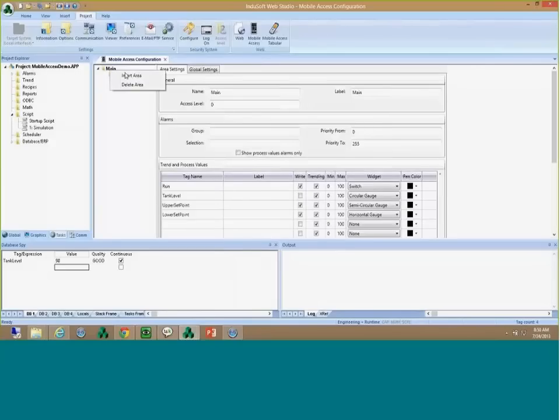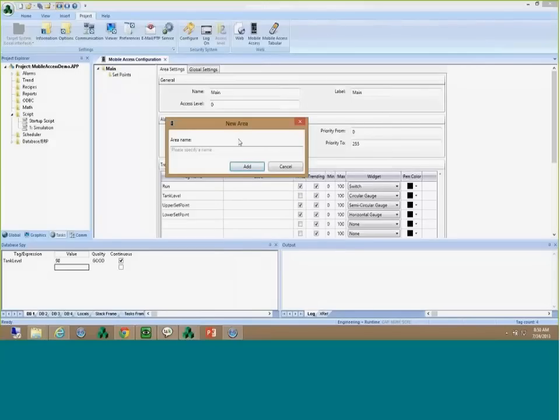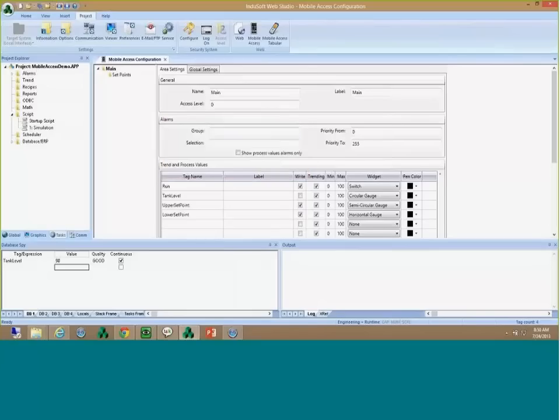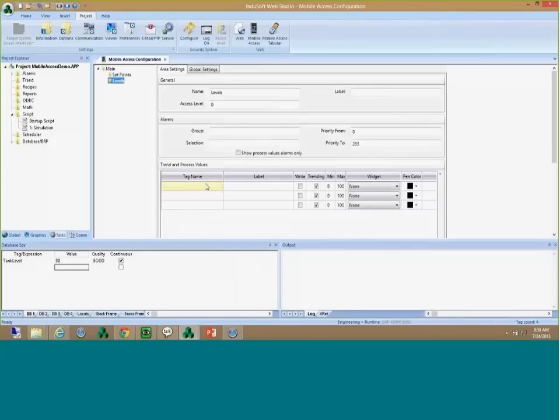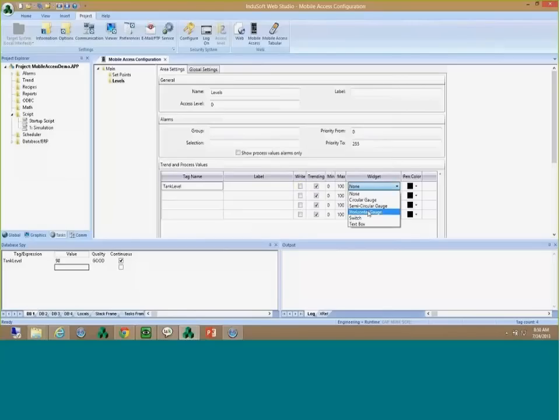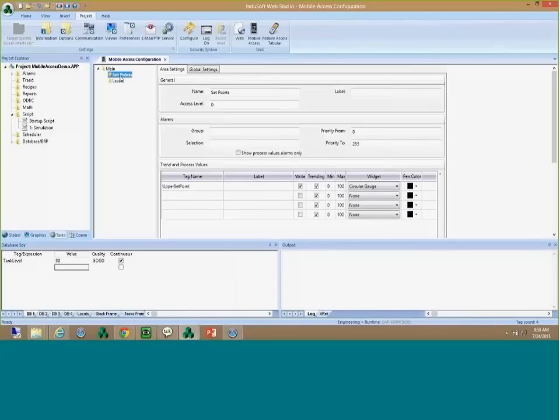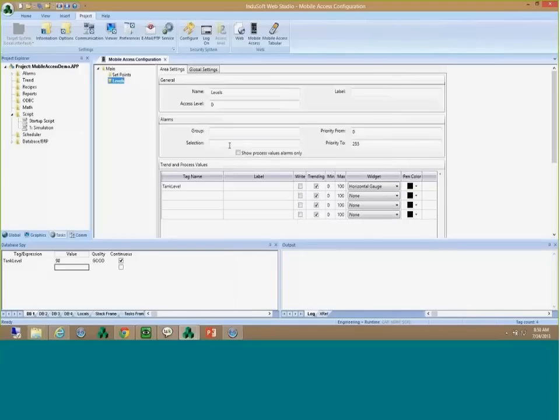For example, in a building automation application you could add one node per chiller or per floor, and inside each floor or area you can have sub-areas. For the 'set points' node, I'm going to copy the set points from main, paste them in, select different widgets if I want, and save it. I'll add another sub-area called 'levels' and add my tank level tag there with a horizontal gauge. For each different area you can have a different alarm filter — I'll specify 'SP' for set points and 'TL' for levels, matching the selection fields I configured earlier.